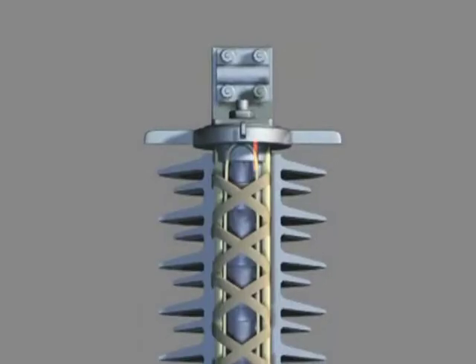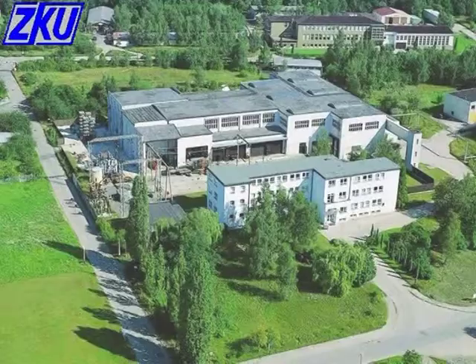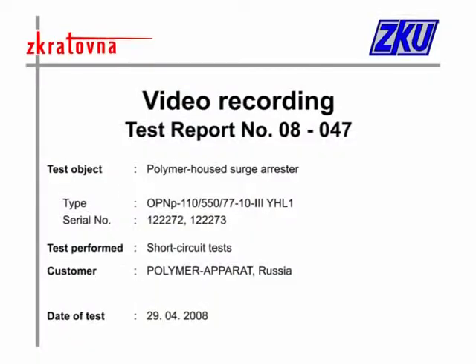The load-carrying structure of MOSA is a cage of glass fiber, which ensures high mechanical strength and full explosion safety. Non-explosiveness of arresters is confirmed by tests in the laboratories in the Czech Republic. Arresters withstand a short-circuit current of 65 kA without explosive destruction.